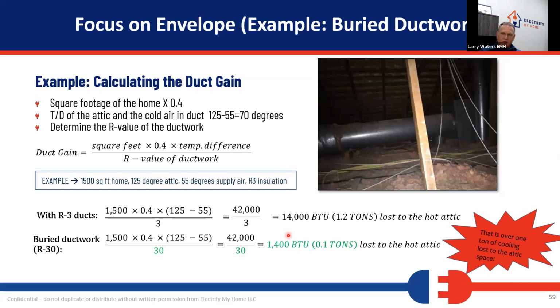There's a secondary benefit to that. What about the benefit of installing the insulation in the attic? When we install the insulation in the attic, that also reduces radiation on the ceiling, which will also, in this particular scenario, reduce by 1/2 ton per hour of heat that's being radiated into the house. So just by doing this measure alone in a house like this, we can reduce the capacity of the system by half. So I don't have to feel nervous putting a half-size system in here if I've taken care of these basic things.